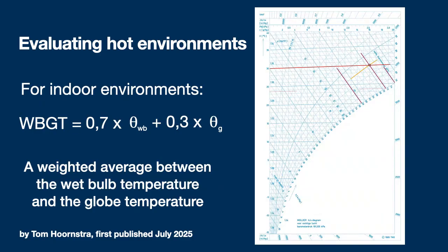Now we have to check what is the wet bulb temperature. Well, the wet bulb temperature lines are the purple-red lines at a 45 degrees angle. So we see the 20 degrees wet bulb and the 25 degrees, but the one that goes through the circle amounts to 23.7 degrees. Now we know that. We continue.